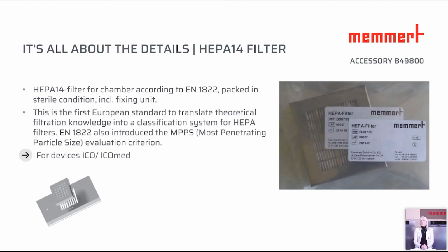So as we know, our CO2 incubators also have a very special feature, the hot air sterilization function, which means it heats up automatically to 160 degrees and holds for hours whenever the hot air sterilization has been activated. Please kindly take out the HEPA filter and, after the sterilization process has been finished, use a new HEPA filter in the interior. So, HEPA filter for removing and for the interior of our CO2 incubator.